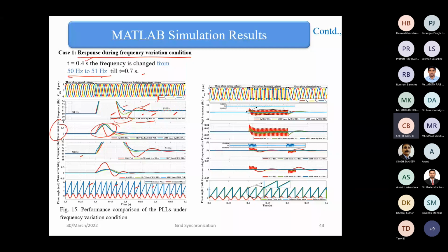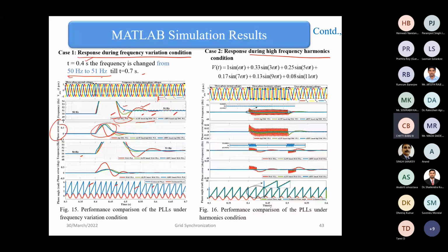This is during high frequency harmonic injection. So we are injecting 33% of the third order harmonic component, 25% of the fifth order, 17% of the seventh order, 13% of the ninth order, and 8% of the 11th order. We are injecting between 0.4 and 0.7. So how is the response with the different state of the art PLLs? You can see that it estimates the value of theta very accurately. So it reduces the steady state error, the settling time, as well as the peak overshoot.